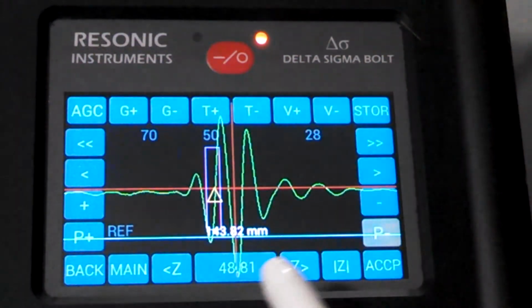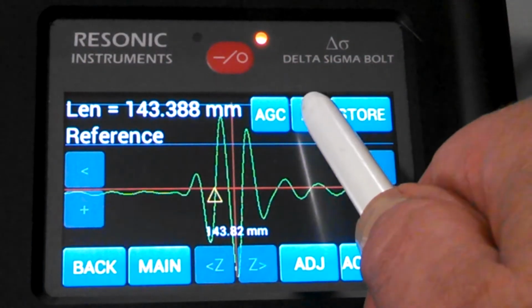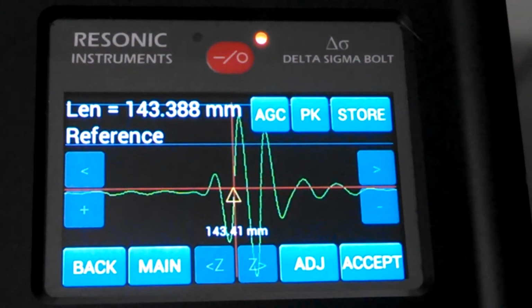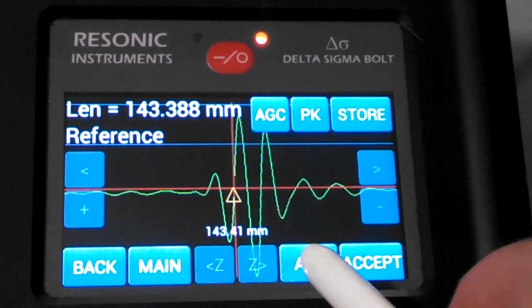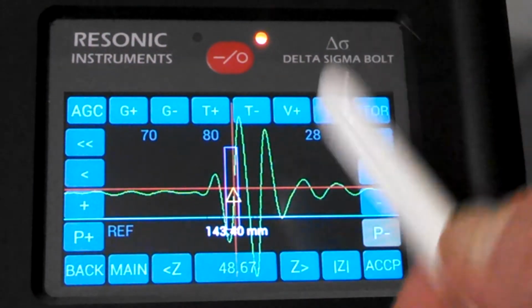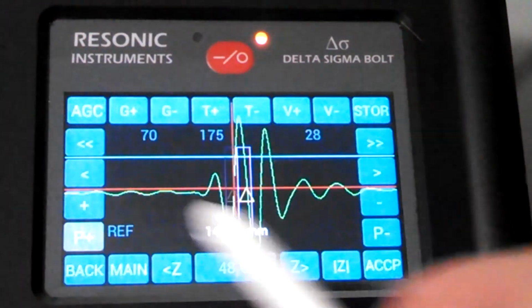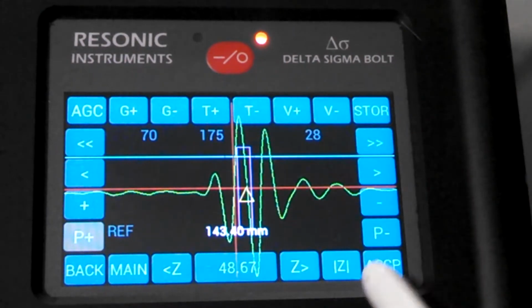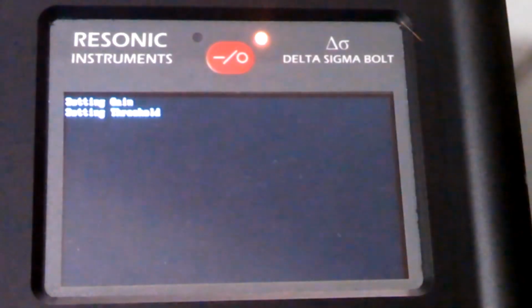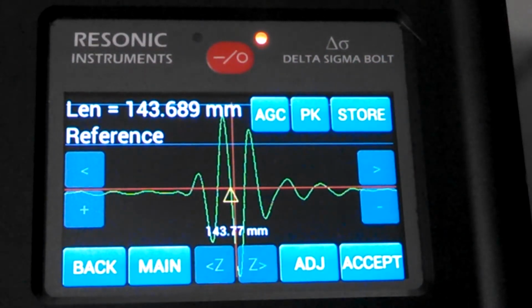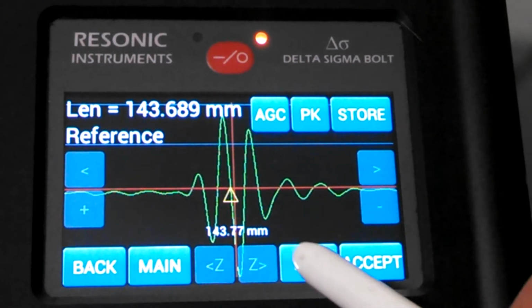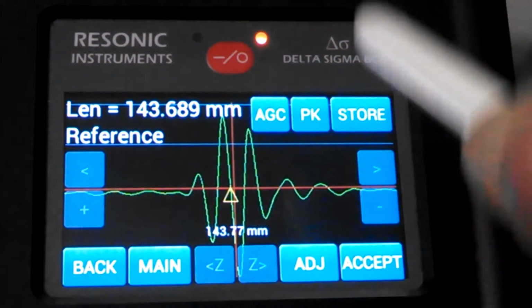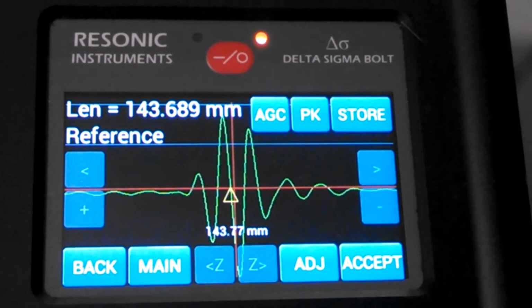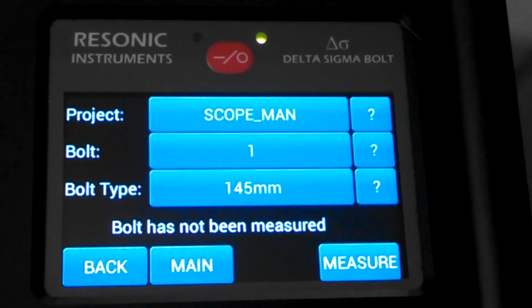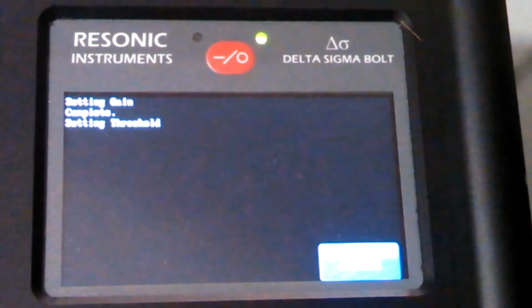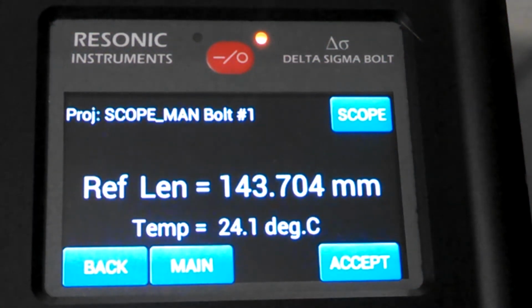Now, if I change the polarity and go back to the main scope and then hit peak again, it's going to go back and use the polarity that you had chosen in the reference in the scope. But we don't want to do that because it's an okay signal. You've got a negative signal here, but the gain is a little high. So we'll hit the positive peak again, go back to the main scope, hit peak again. It'll go back and readjust the whole signal again and give you the original setting. So if you get lost in the manual scope mode, hit the adjust button, go back to the main scope, hit peak again, and it'll reset. If you're in your reference length, you just go back and back out. It'll redo the whole bolt again. So until you store the reference length, it does not remember the receiver settings.